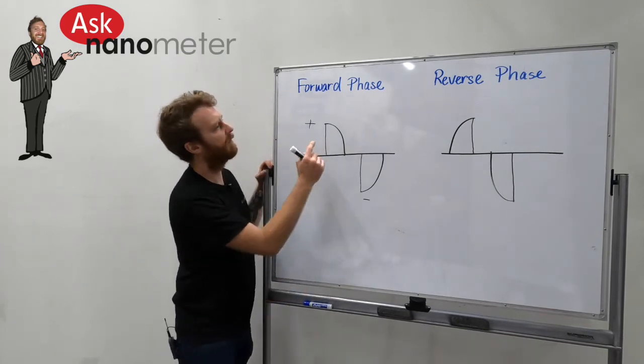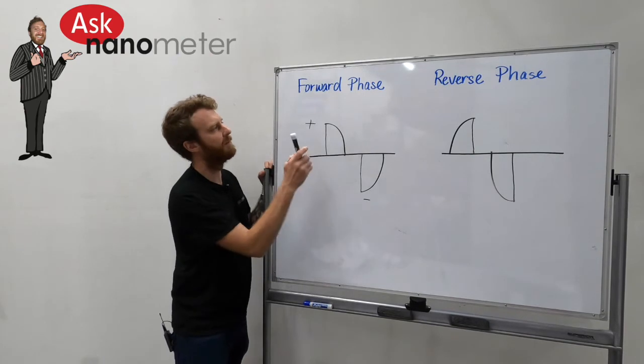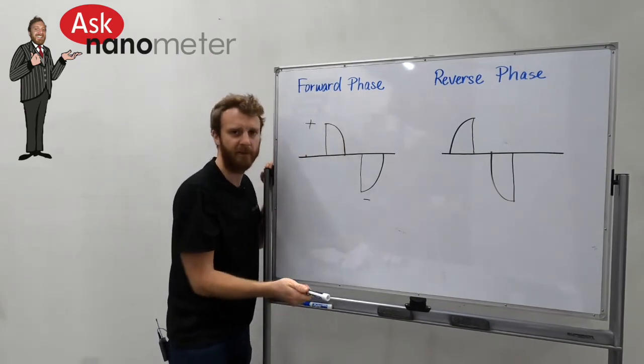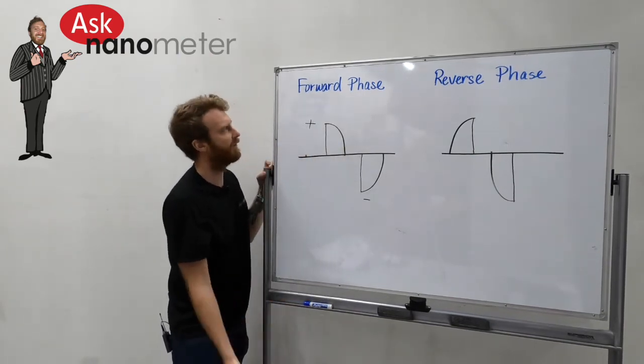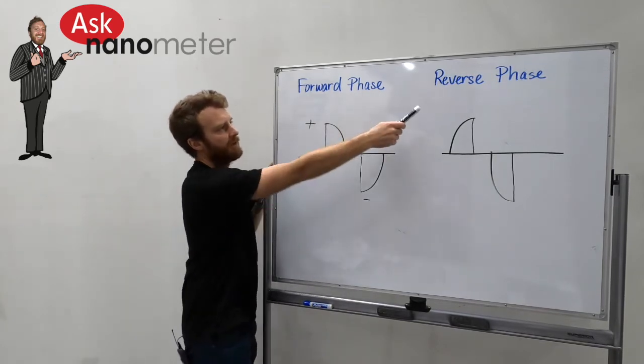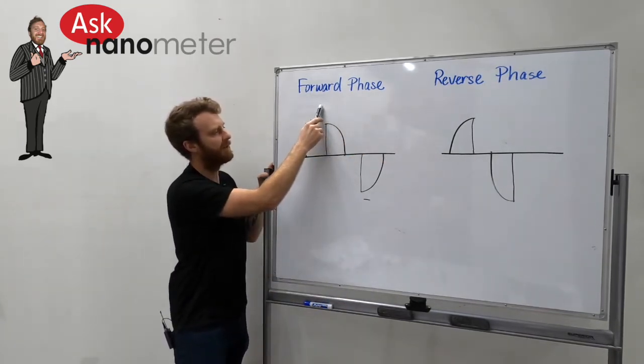A couple of things that can trip you up on this: if you pair the wrong type of dimmer with the wrong driver. If I take a reverse phase driver and attach it to a forward phase dimmer, the reverse phase driver is expecting to see this gentle climb to maximum potential.